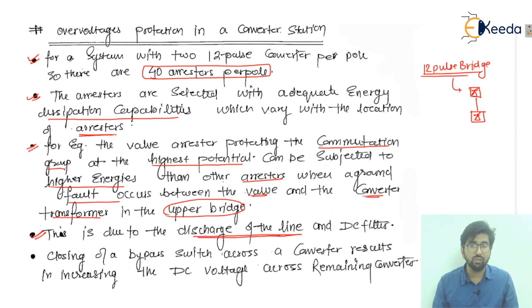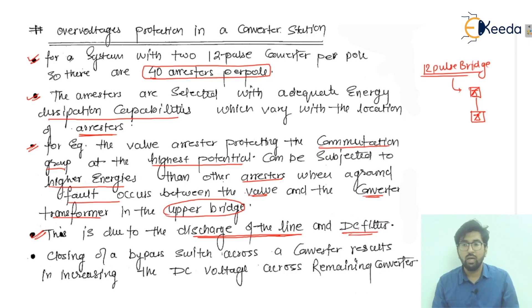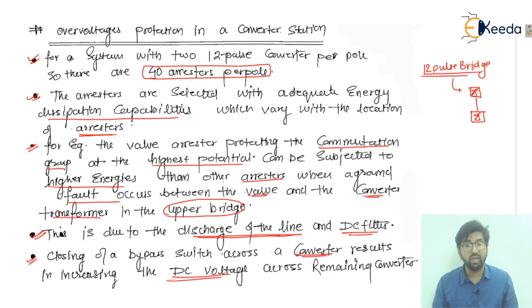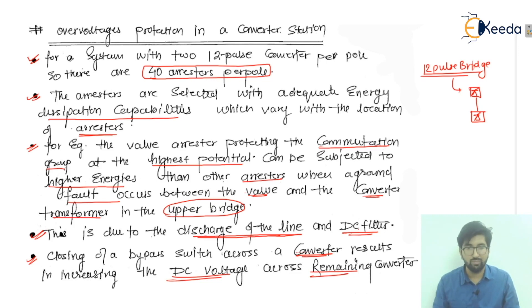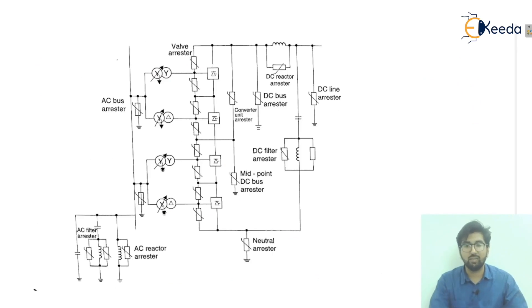There will be a carry of charges and the discharge will take place from the line, and also from the DC filters. The closing of the bypass switch across the converter results in increasing the DC voltage across the remaining converter. So when the bypass switch is in the closed condition, it will affect the other converter by increasing the DC voltage across it.